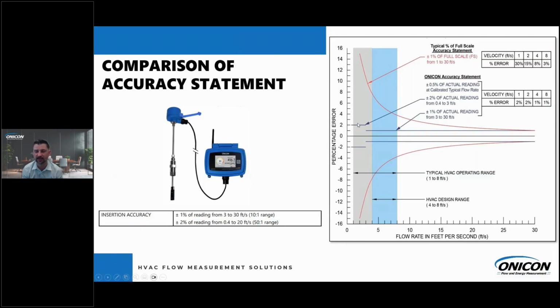I like to put that in a quick example because we get this question all the time. Hey, this looks like a 1% device, can you tell me what the difference is? Well, let's say you have an application and both meters can read 0 to 5,000 GPM, but you're trying to measure 300 GPM. A 1% of full scale device is going to be 1% of 5,000, or plus or minus 50. When you're trying to measure 300 GPM and your flow meter is plus or minus 50, that's not very accurate. All ONICON meters are percentage of reading devices. So in this case, 1% of 300, or plus or minus 3, makes a big difference.